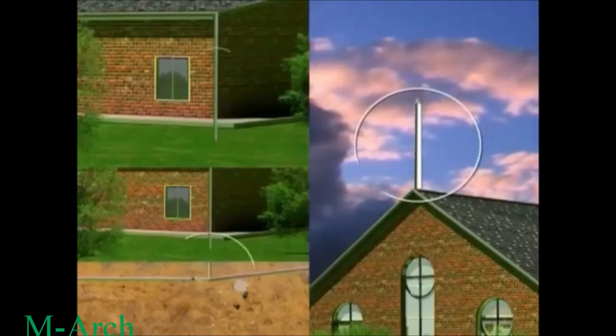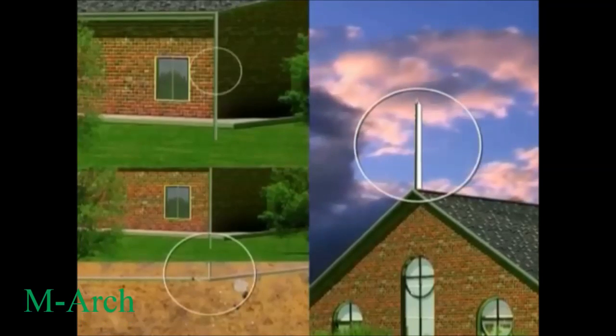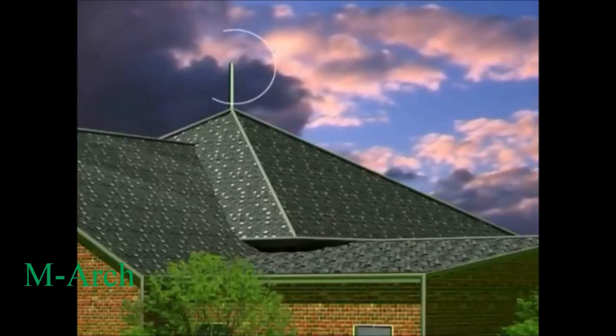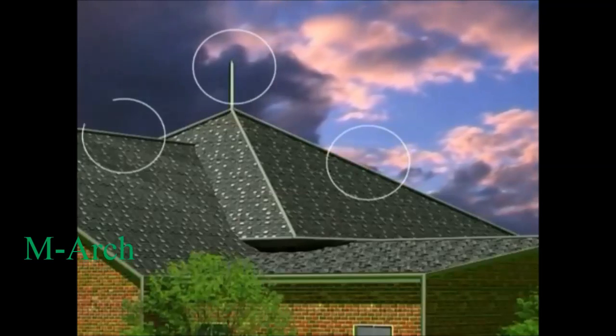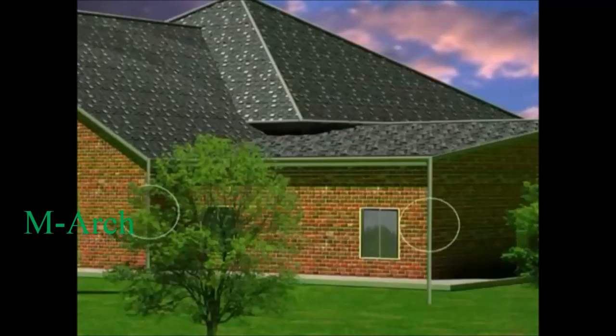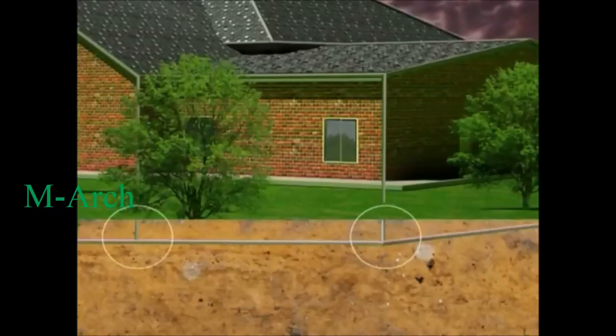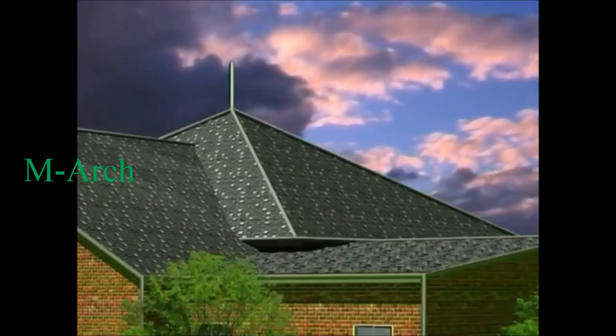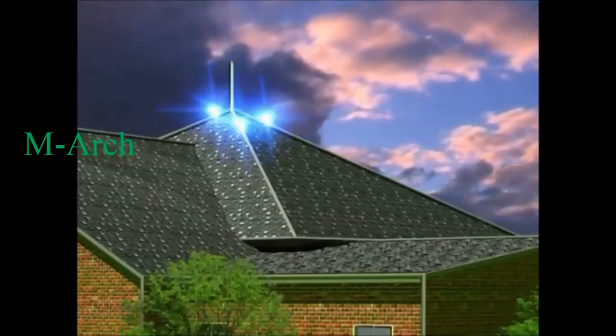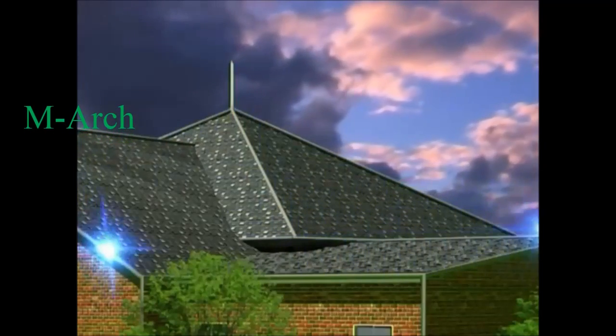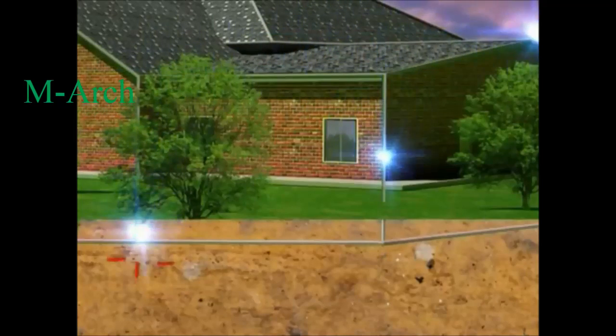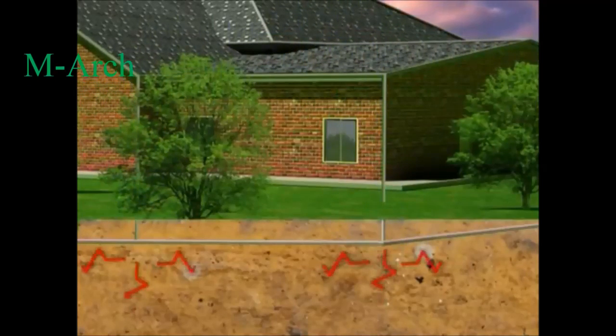Lightning-conducting systems can be classified into two: external protection systems and internal protection systems. The external protection system consists of three main components: air terminal or interceptor placed above the building, down conductor, and earthing. In this system, the electric charge from the lightning is received by the air terminal and is sent through the down conductor and further to Earth through the earthing system.